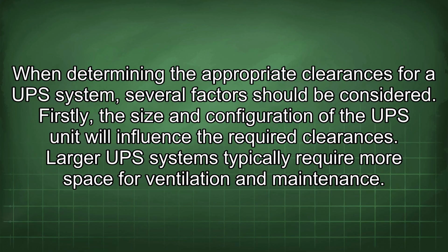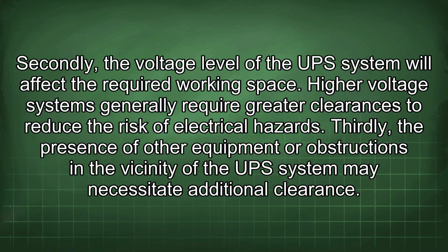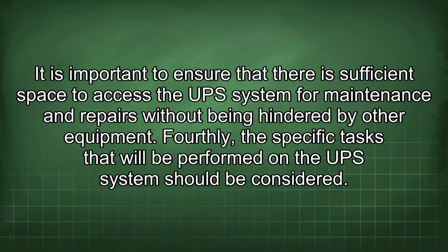Firstly, the size and configuration of the UPS unit will influence the required clearances. Larger UPS systems typically require more space for ventilation and maintenance. Secondly, the voltage level of the UPS system will affect the required working space. Higher voltage systems generally require greater clearances to reduce the risk of electrical hazards. Thirdly, the presence of other equipment or obstructions in the vicinity of the UPS system may necessitate additional clearance. It is important to ensure that there is sufficient space to access the UPS system for maintenance and repairs without being hindered by other equipment.